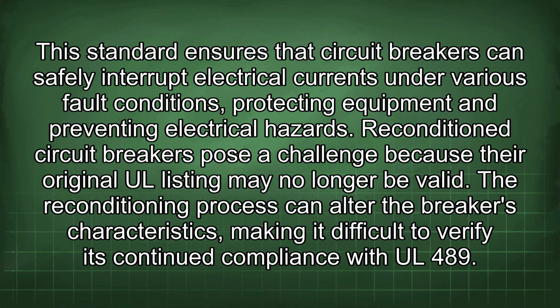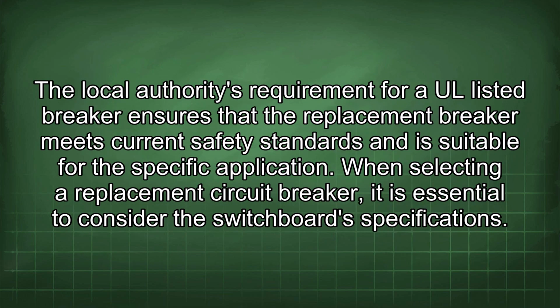Reconditioned circuit breakers pose a challenge because their original UL listing may no longer be valid. The reconditioning process can alter the breaker's characteristics, making it difficult to verify its continued compliance with UL 489. The local authority's requirement for a UL-listed breaker ensures that the replacement breaker meets current safety standards and is suitable for the specific application.